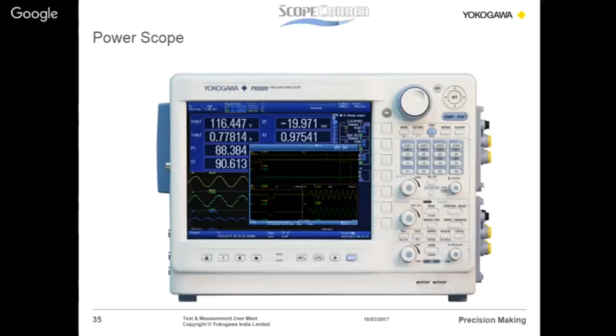So this is the front panel. It can be configured with up to 4 power channels. One module will be voltage and another one will be current. So one voltage module and one current module are calibrated as one set, so that they serve as one channel. Like that it can be configured up to 4 channels, and it's a 100 megasamples per second module. Auxiliary input can take up to 20 volts, with noise immunity, and 20 megahertz bandwidth.